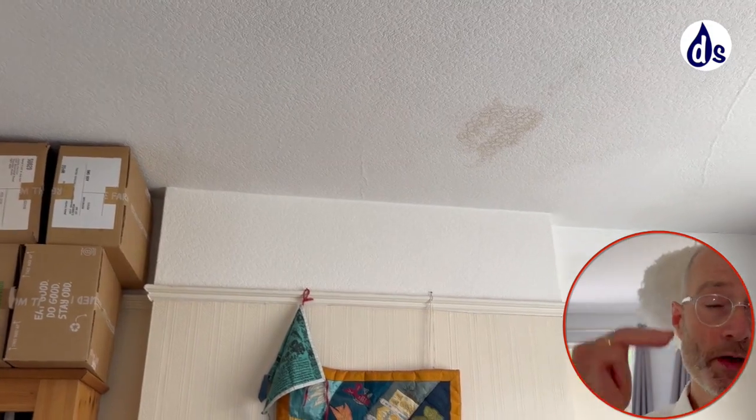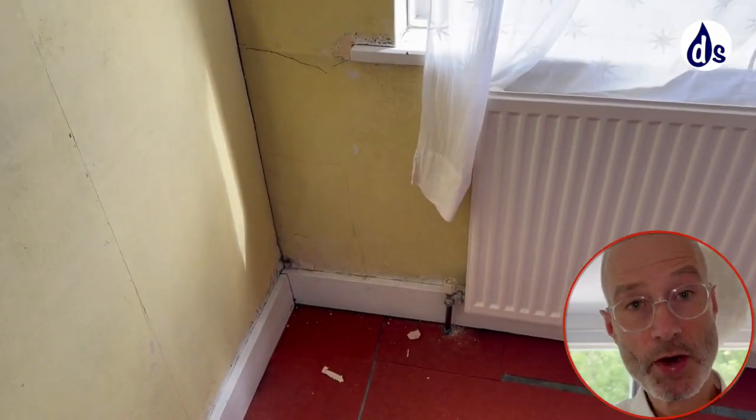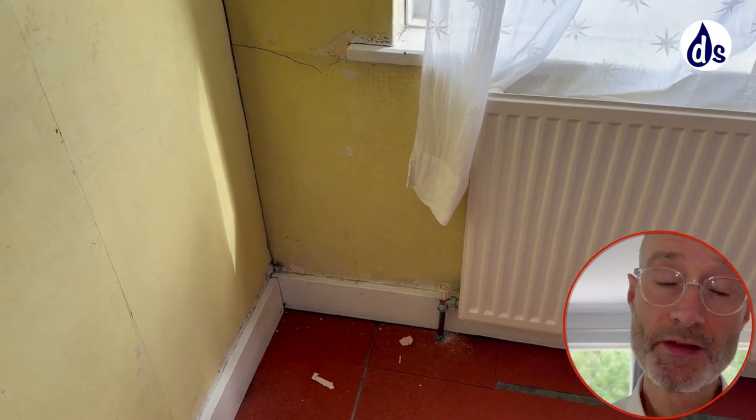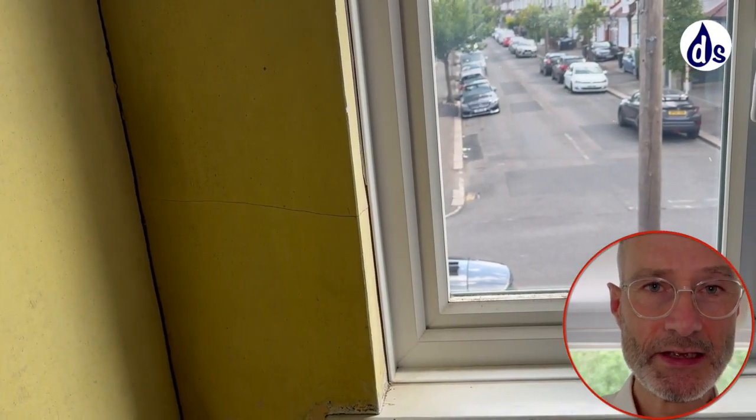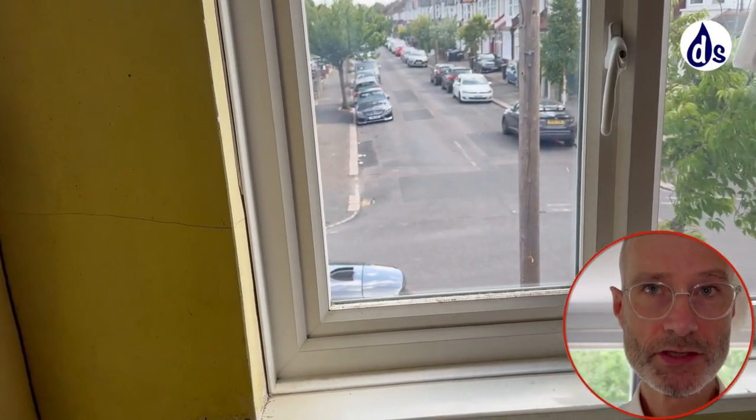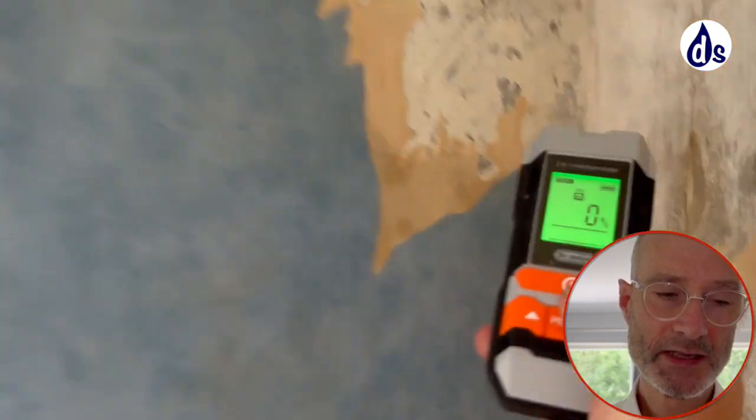There's a room to the front, which I think you occasionally use as a study, but don't heat very much, and that's getting lots of mould. It was dry at the time of the survey, but that will be from excess vapour, primarily from the bathroom. But the kitchen didn't have an extractor fan either, and you do have a dehumidifier, but it's the one that's suitable for low temperature.